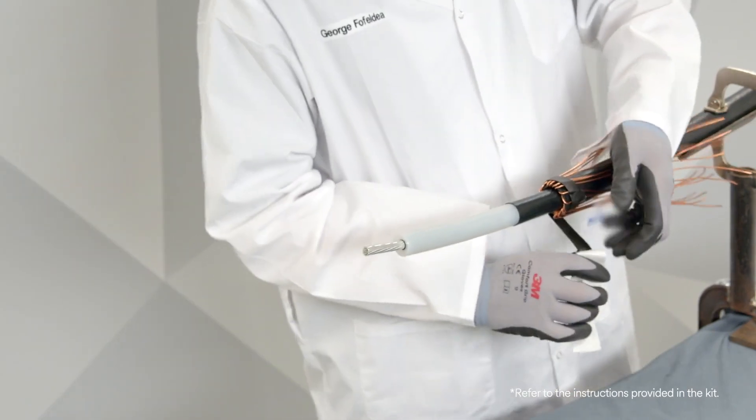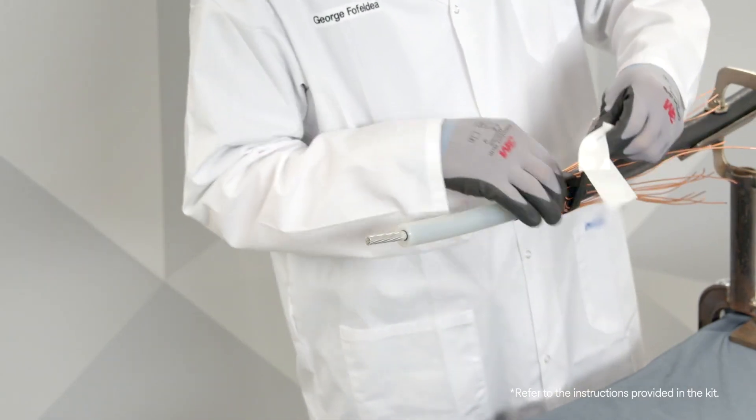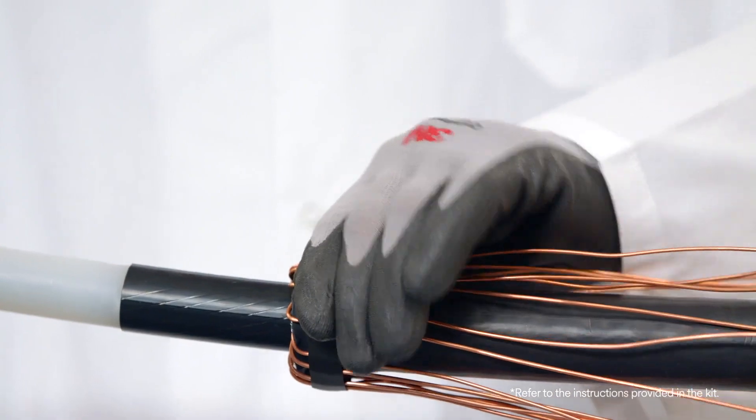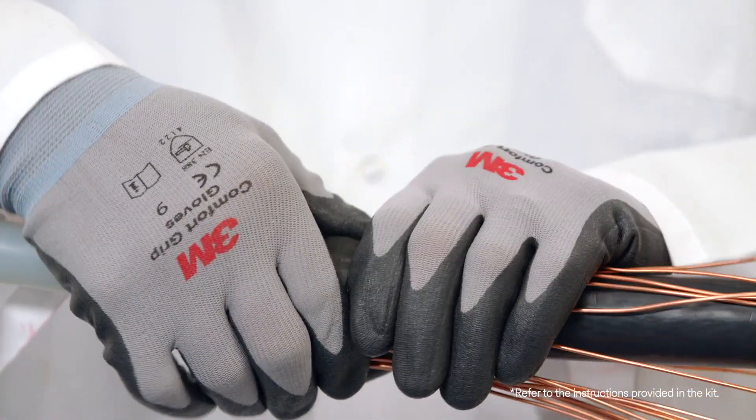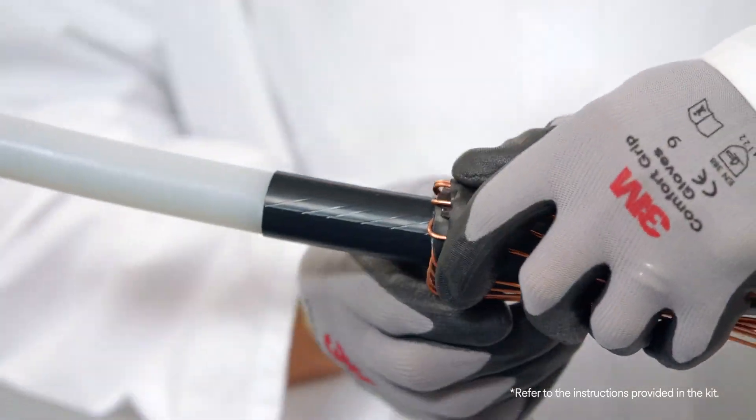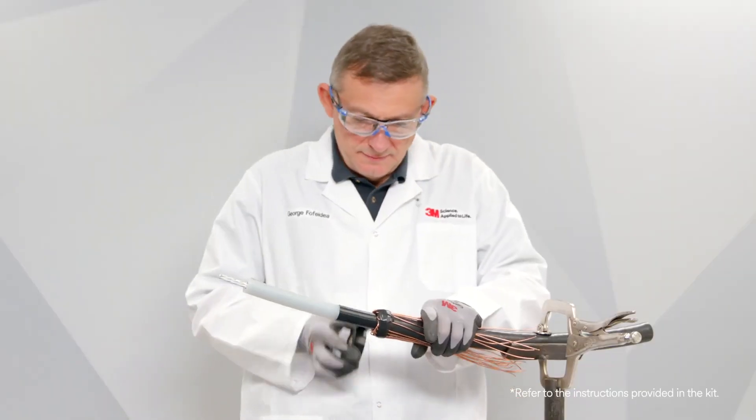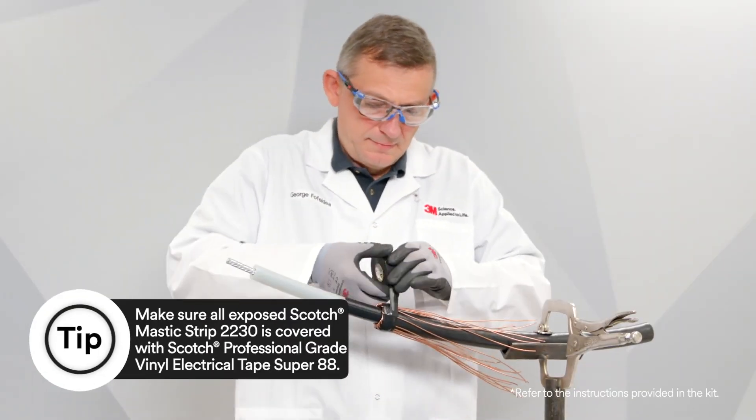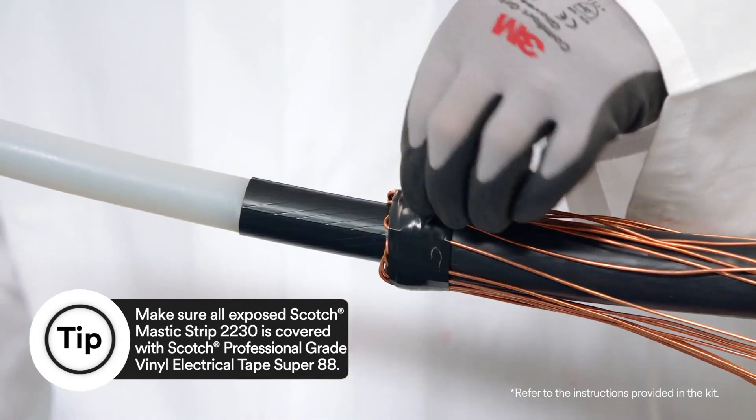Now apply a single wrap of the Scotch Mastic Strip 2230 over the neutral wires and then compress neutral wires into Scotch Mastic Strip 2230 by over wrapping seal strips with two highly stretched layers of Scotch professional grade vinyl electrical tape super 88.